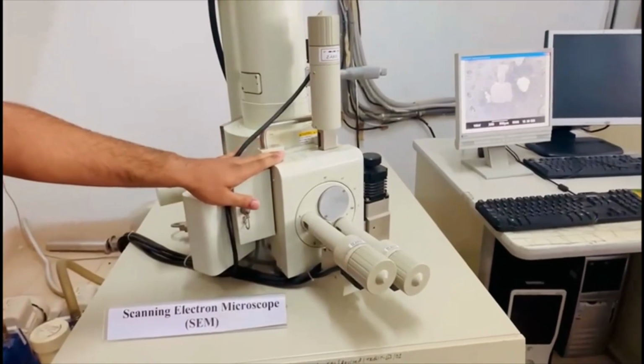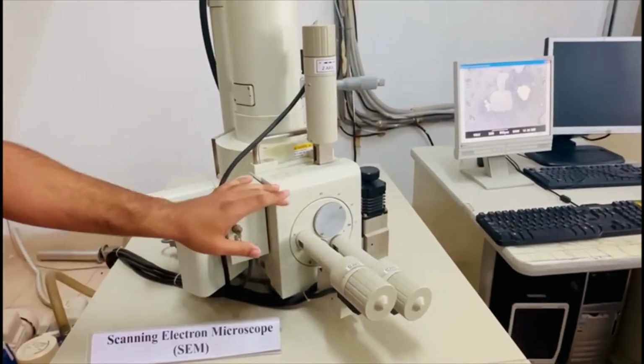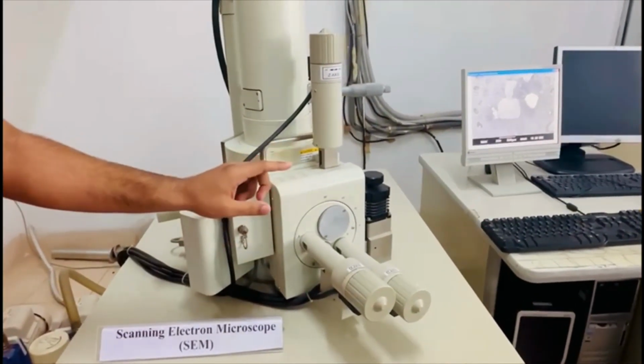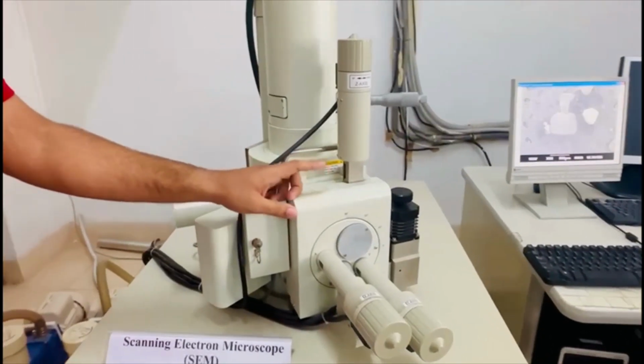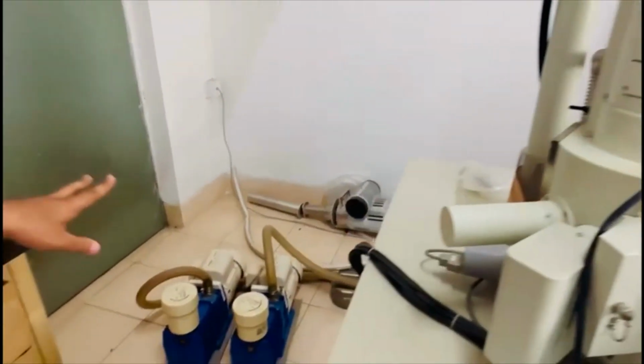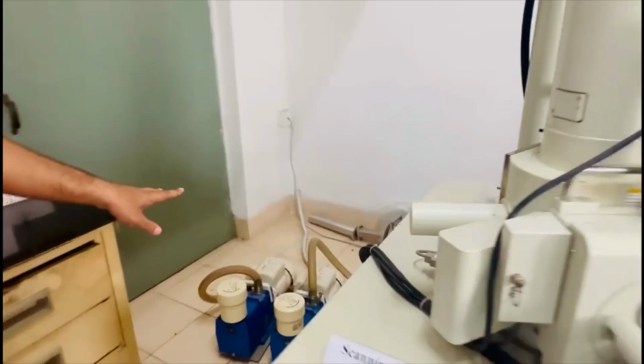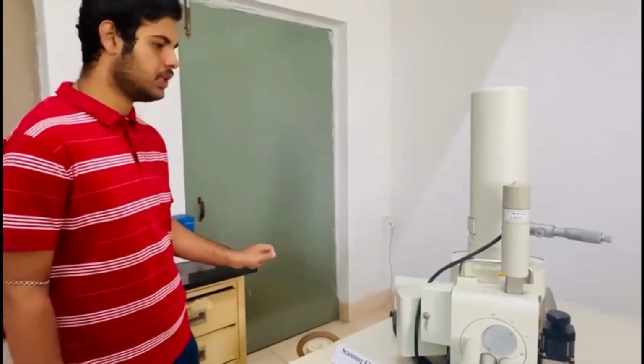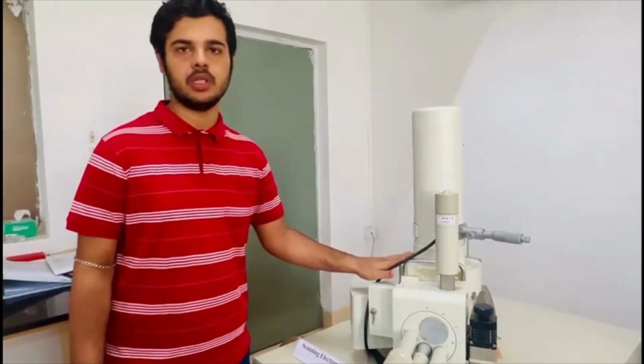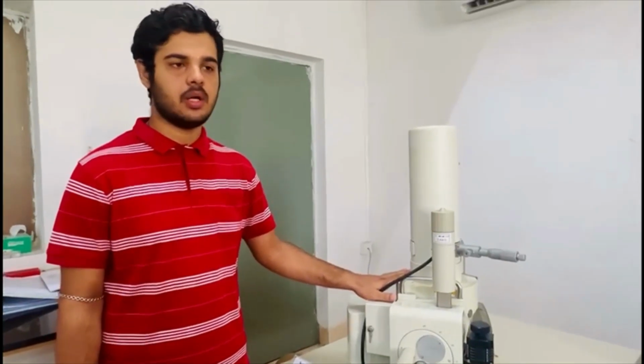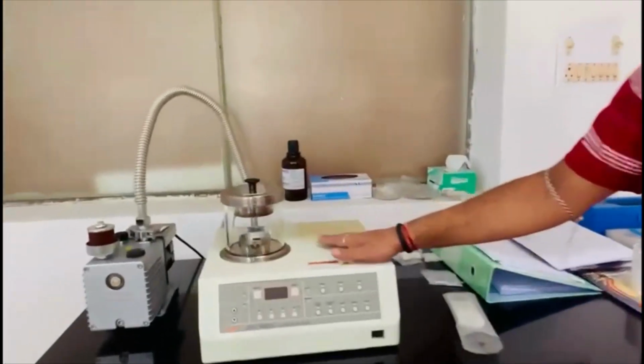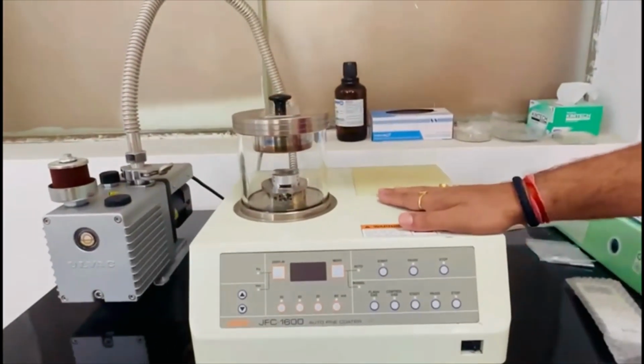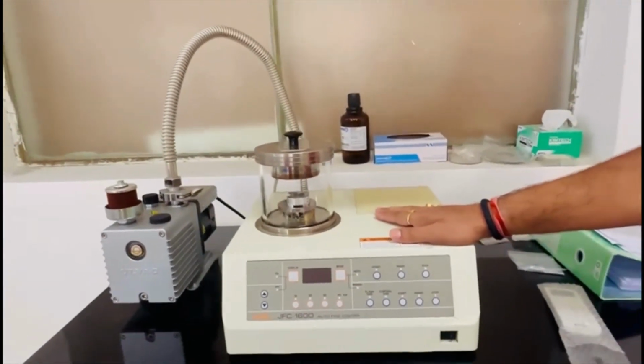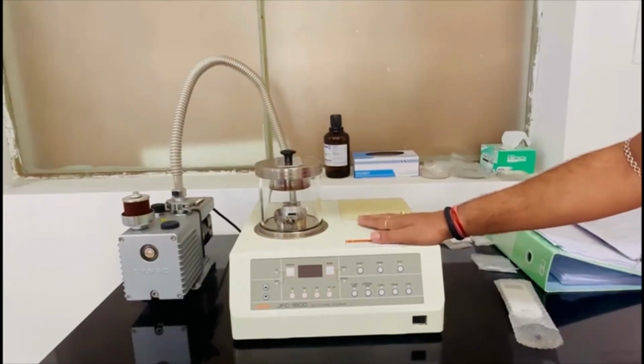The machine has 5 axes which are X, Y and Z, R and T, which are the axes of movement, rotation and tilt respectively. These are the 2 rotary pumps which can achieve a vacuum of 10 to the power minus 3 millibar. Usually the sample should be conducting for SEM, but if the sample is non-conductive, we coat the sample using this machine which uses the principle of sputtering, and the images are taken like this.